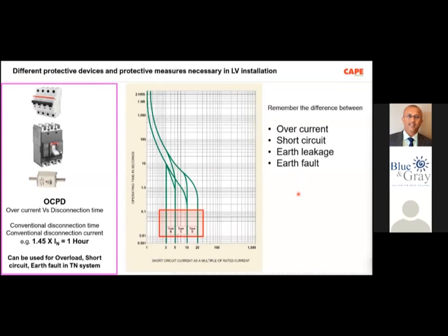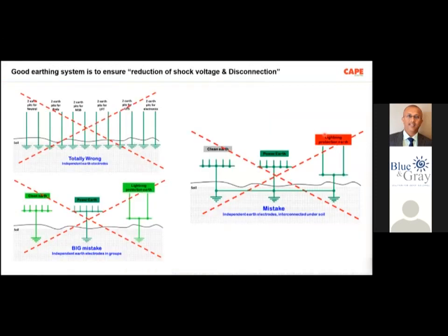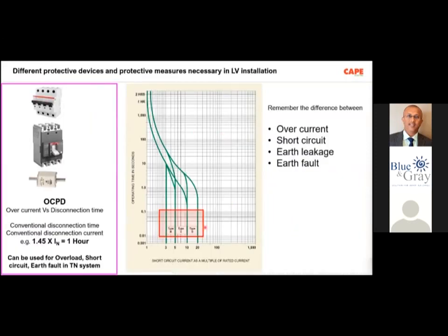So an insulation reduction between two current carrying conductors is usually called overcurrent or short circuit, whereas a fault between a live conductor and the earth, meaning a metallic body which is not a current carrying conductor, is called an earth fault. So we are talking about automatic disconnection, we are talking about earth fault. Of course, for the first two, overcurrent and short circuit, other curves are applicable, and the wiring also should withstand all these things.